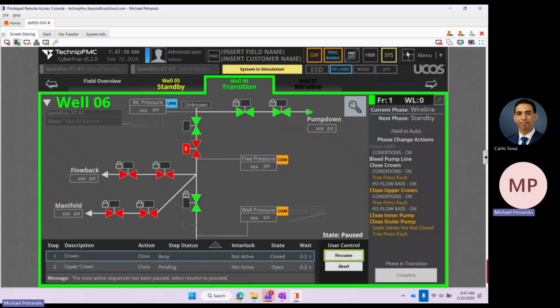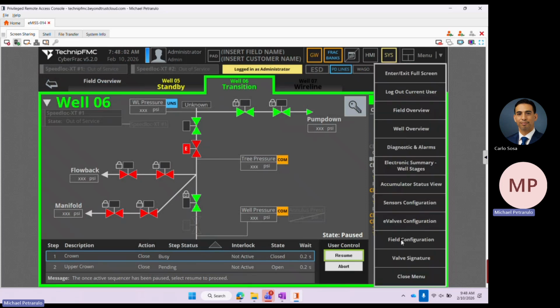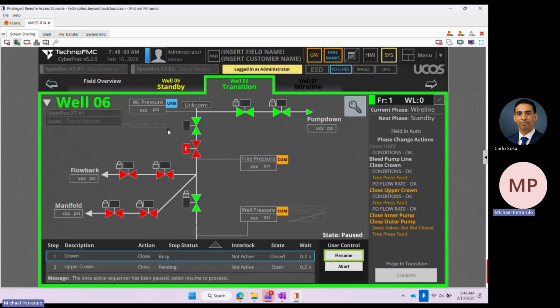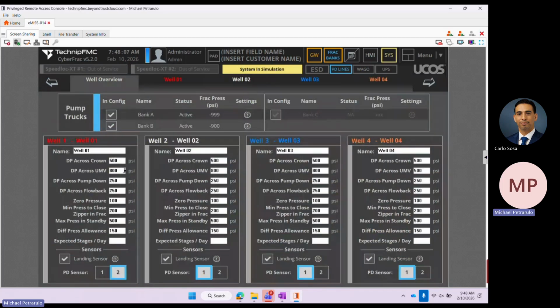Yes, and that's where all these set points come in. We could probably have a separate video on that explanation, just what do all of these mean. But that's where my calculations are based off of. It's like, hey, you're allowed to be equal to or greater than 500 psi, DP across UMV, different valve, different phase change. So maybe I have a different set point, so I say, oh well, UMVs can support a higher pressure differential. That's all defined by the customer and how they want to handle it.